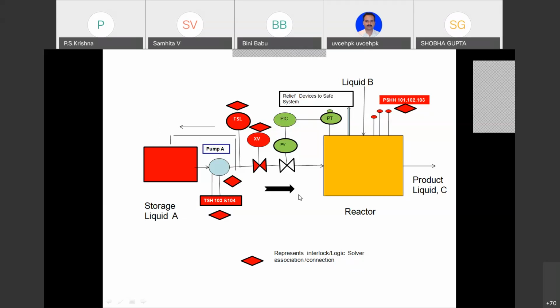The instrument guys did what is known as a hazard analysis. Who are the people who attend the hazard analysis? One, the process engineer. Two, most important, the instrumentation and control engineer, he has to be there. Then the mechanical man, the piping man, and depending upon the kind of job, electricals will come in, and some other specialists will also come in. You know what a hazard study is all about: they go line by line, step by step, and they ask what happens if the pressure goes high? What happens if the flow goes high? What happens if the temperature goes high? What happens if the pressure is normal? What if the flow is normal? And when the temperature is normal?